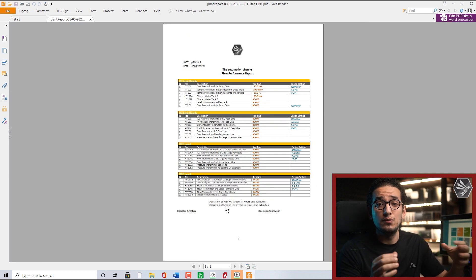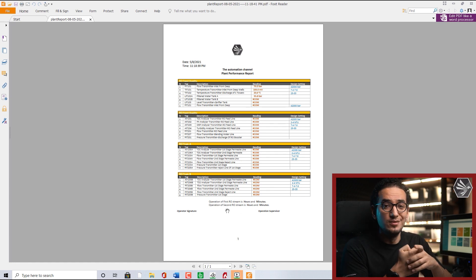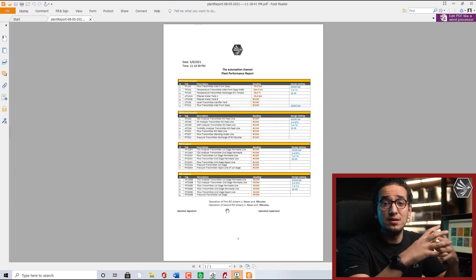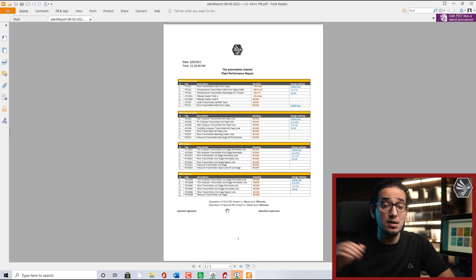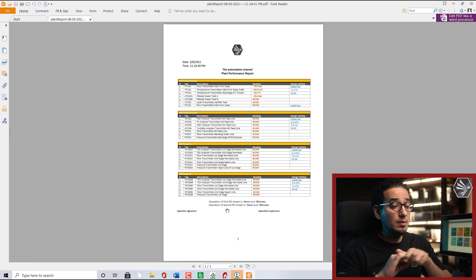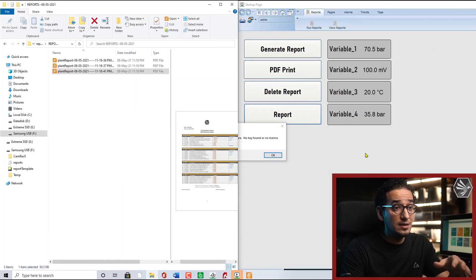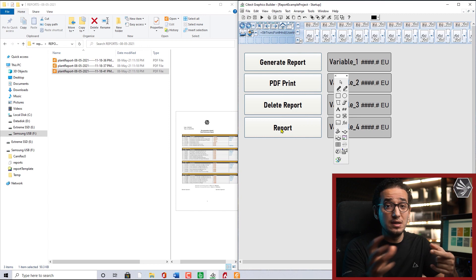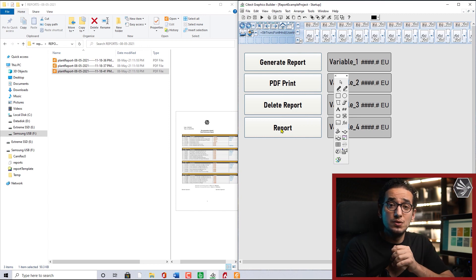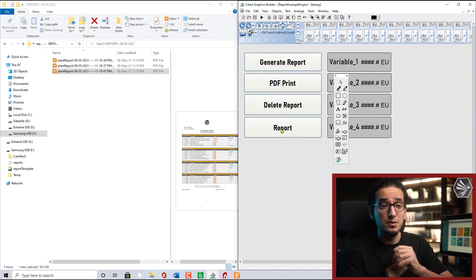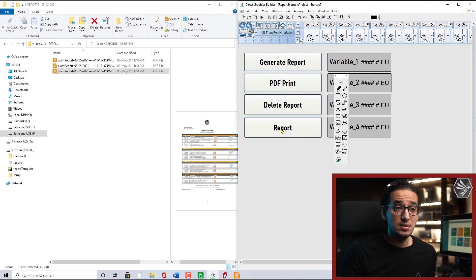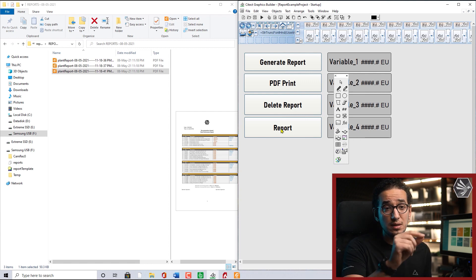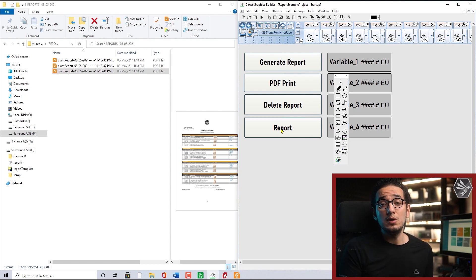One more thing - in the operation of the water treatment plant, you see the guys are using walkie talkie just to transfer the values once they have a central SCADA only. There is no SCADA or HMI in the RO building or filtration building. The operator, while he's sitting, can simply trigger the report through one button and then send it through WhatsApp rather than keep using the walkie talkie to communicate the readings.